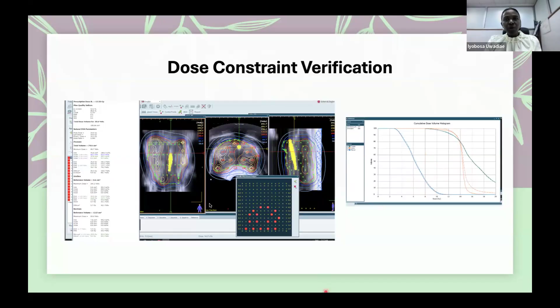We also check the physics data, the source, the type of source, because our system is a Bebig system that can take both an iridium and a cobalt source. So we also check, because sometimes I've had cases where we have a cobalt source, but the system is calculating using an iridium source. So we always make sure that before treatment delivery, we verify all these parameters.